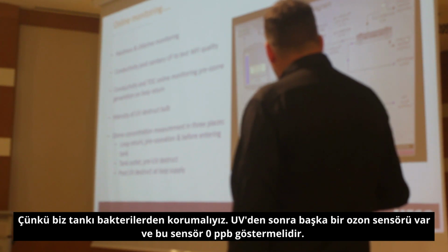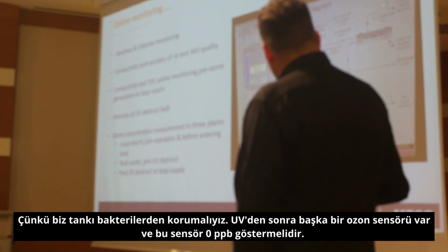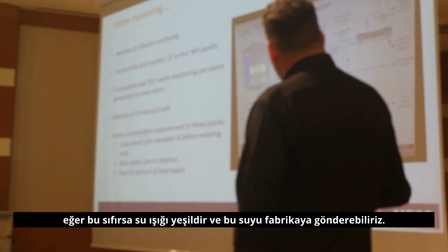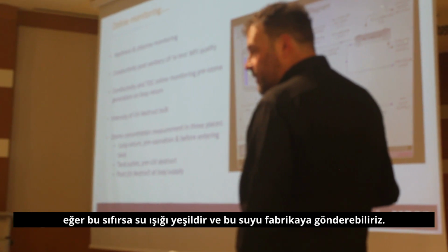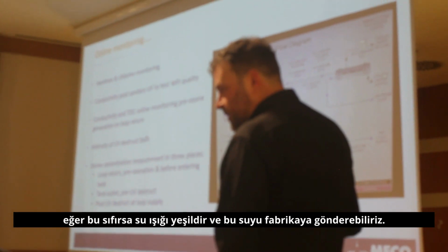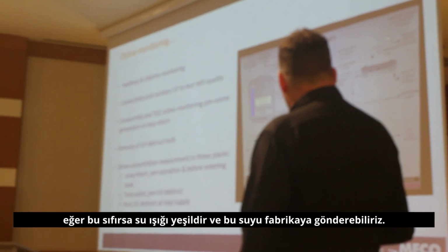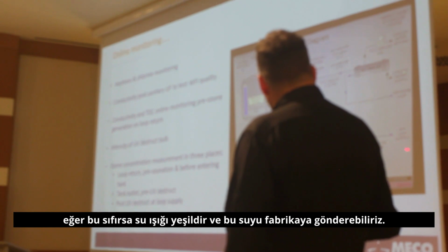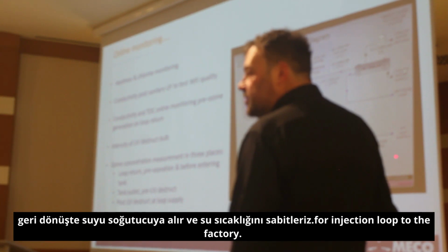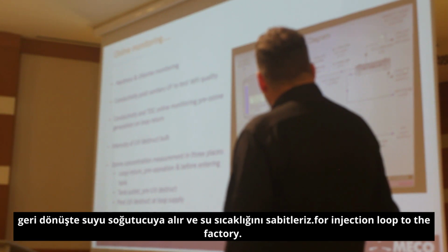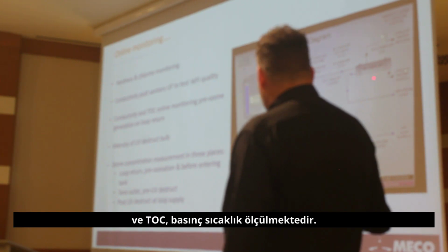After the UV, we have another ozone sensor which must read 0.00 ppb. This is all automated, so if that is 0, the light is green, and we supply our water for injection loop to the factory. On the loop return, we come to our chiller because we need to keep the temperature stable.